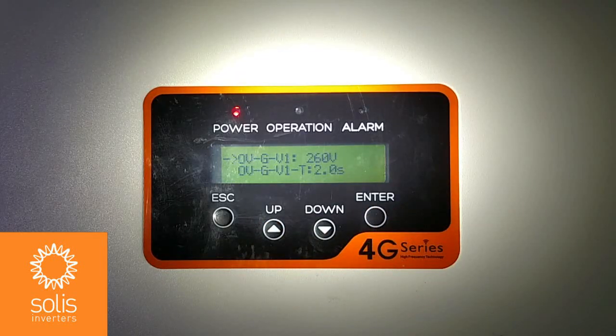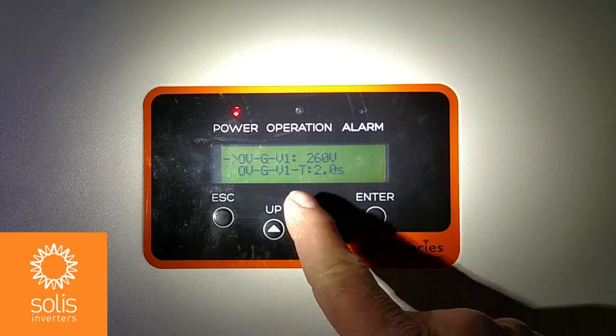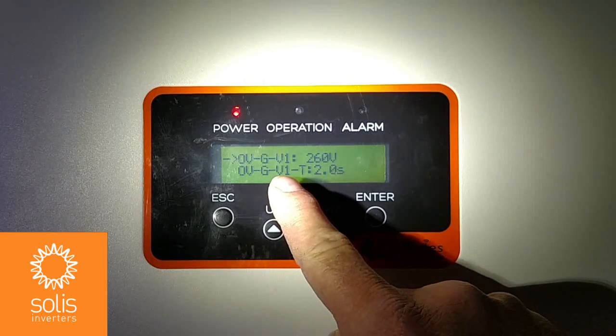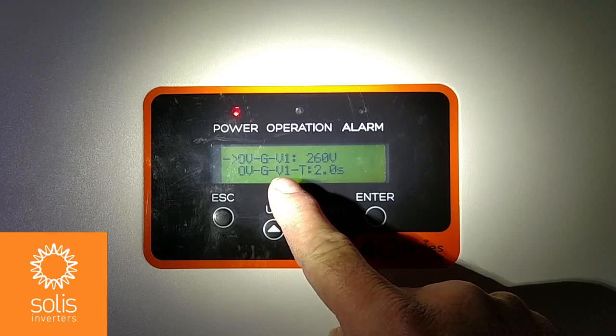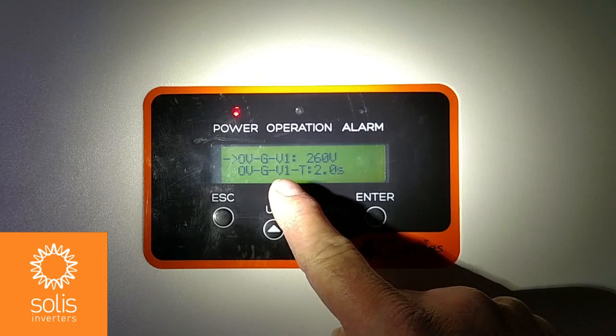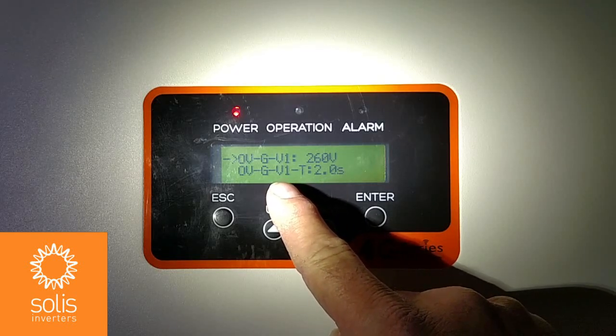Now, in this menu, you'll notice that we can change not only the trip limits, but we can also change the trip times. And you will note that there is a 1 here after the V indicating voltage. That indicates we're going to adjust our intermediate trip limit and trip time.